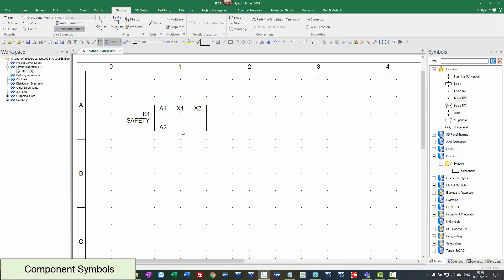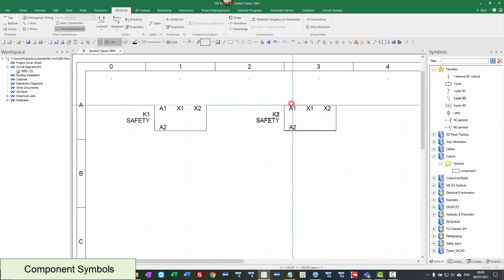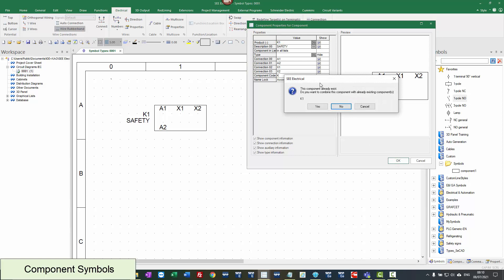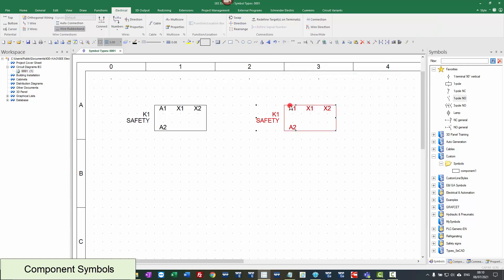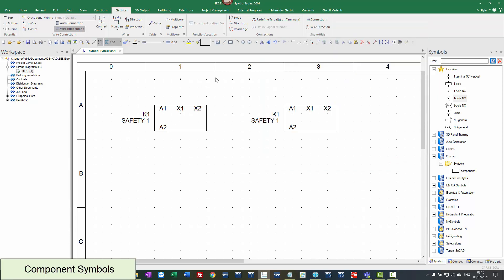One enhancement we can make is to take this one, right click and choose copy, then right click and choose paste. If I paste it a second time, it gives it the next available identification. If I double click and change it to K1, I get a message: 'This component already exists.' It warns me and says, do you want to combine this component with the already existing one? If I click yes, in the project database there becomes just one entry for these two symbols — they share the same part number and any description changes are reflected in both.